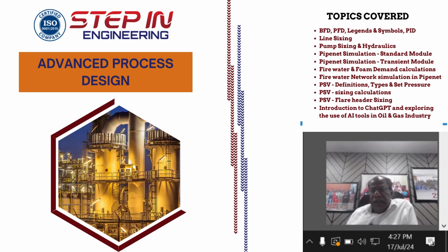Transient surge is a very important topic, because in any project or running plant, the pump may suddenly trip. When the pump trips, what is the impact on the piping system? What is the impact on the discharge pressure? How will the network behave? Can the entire piping design withstand it? There will be a sudden increase in pressure, and to what extent it will reach we don't know unless you do the transient simulation.